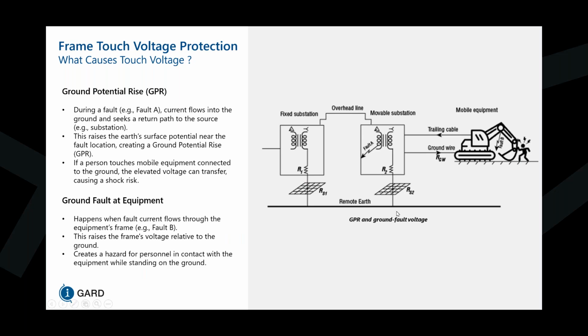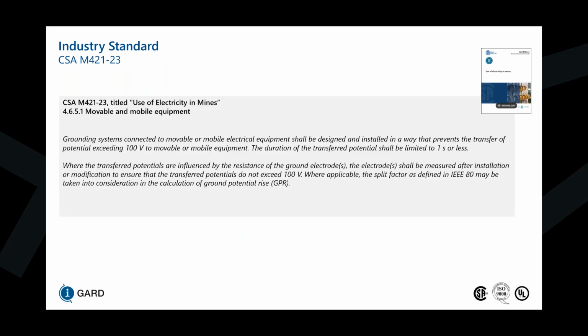So it happens when fault current flows through the equipment's frame, right here, fault B, and this raises the frame's voltage relative to the ground. It creates a hazard for personnel in contact with the equipment while standing on the ground. So in the M421 standard, it requires you to limit the transfer of potential to 100 volts or less to movable or mobile equipment. It has to be limited to 1 second or less, and the system should prevent this transfer of potential.